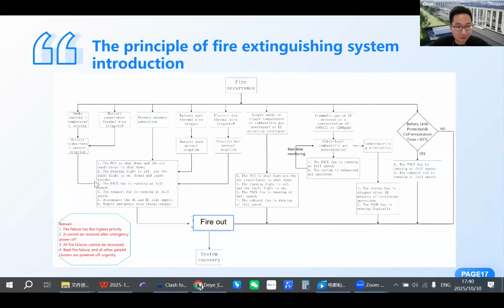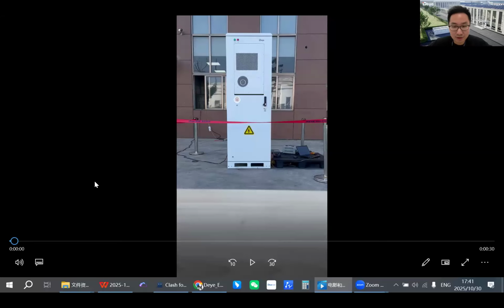Say the situation only calls for extracting the fumes, extracting the combustible air, and the system can still be salvaged. We will only open the exhaust port to extract the smoke and combustible gas, and we will not trigger the aerosol dispenser or the water sprinkler, so that the entire thing doesn't just go to waste. It's only when things get really serious that the final measure will be taken, basically. And I can show you a little bit of something. I think you've seen it in the previous slides. That's what we call the GF60. It's our first generation C&I cabinet, and I will show you what the fume extraction looks like.